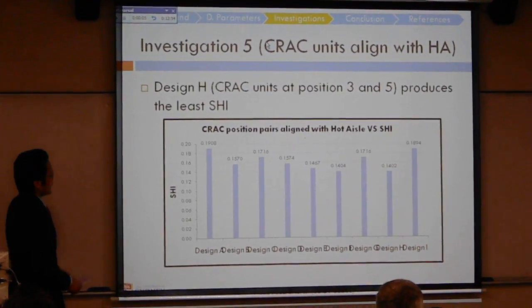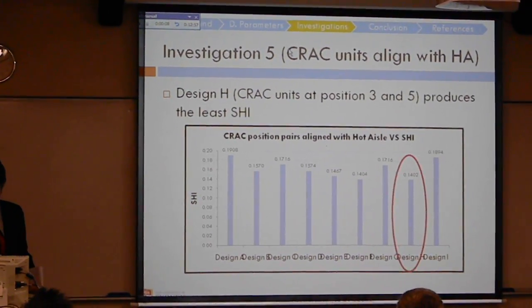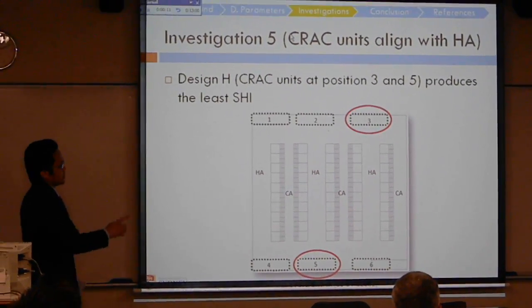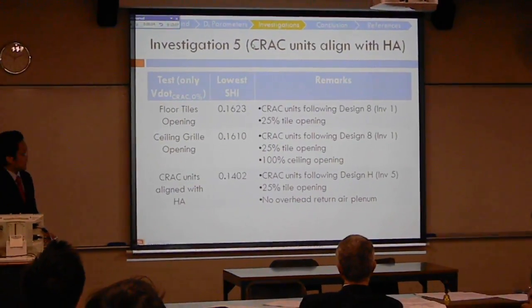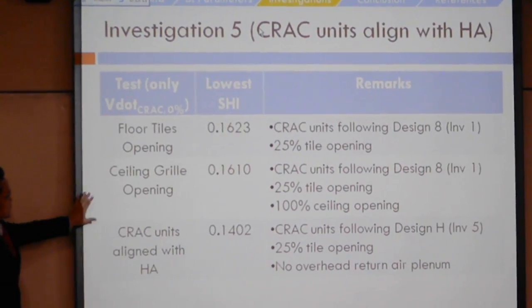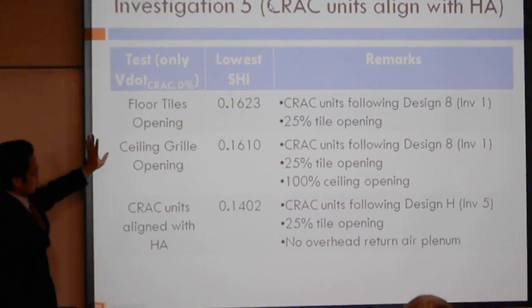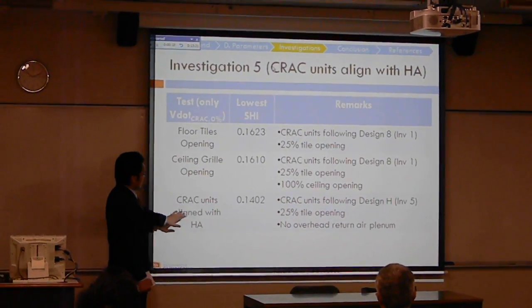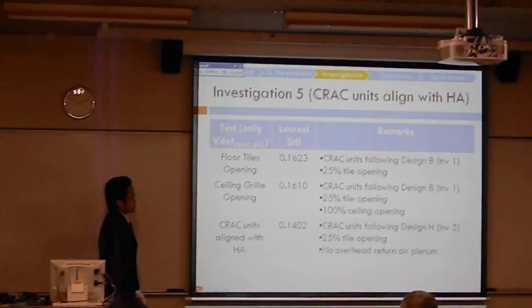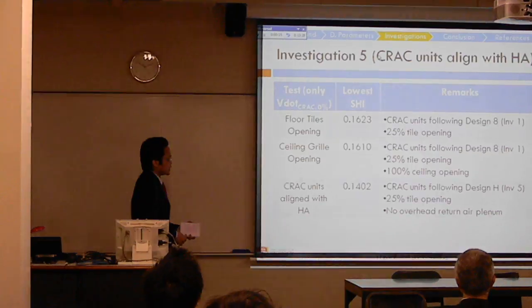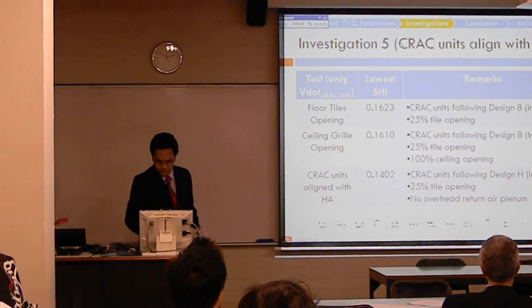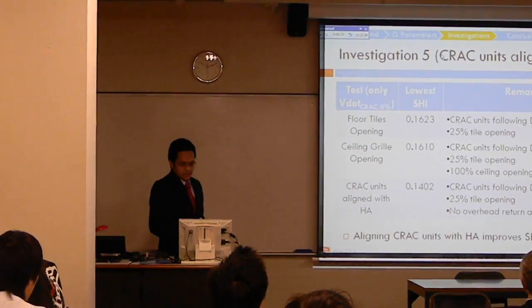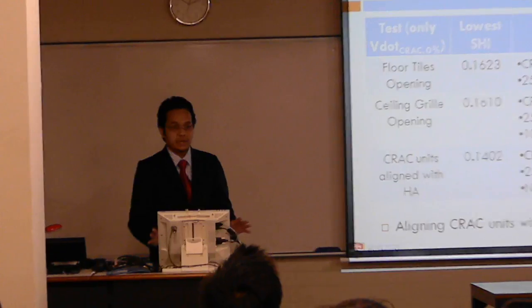The result shows the configuration with the lowest SHI at the following positions: Position 3 for CRAC 1 and Position 5 for CRAC 2. This is the comparison between Investigation 5, Investigation 4, and Investigation 3 — there is a significant reduction in SHI value. For Investigation 5, the lowest SHI obtained is 0.1402. Aligning CRAC units with the hot aisle can improve the SHI by 15%, particularly for this study.